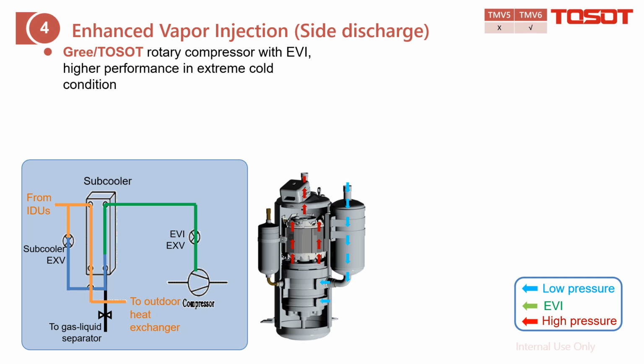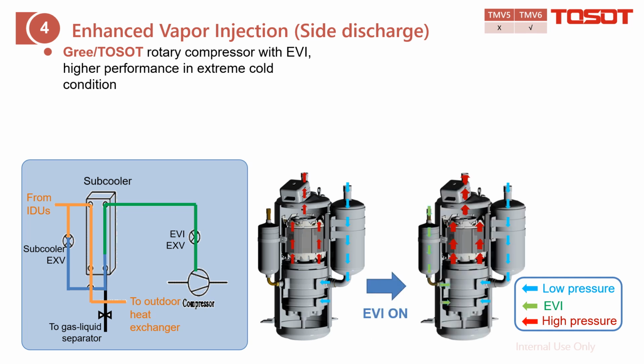As for the compressor, it is from Gree, it is rotary, and this is the regular one without the EVI, which has one inlet. After getting inside, it will get compressed and then get out. After we turn on the EVI, another inlet will join here, then we can make the refrigerant to be compressed out. For this one, you can find that we can get a higher refrigerant flow rate. On the other hand, that means we can get a higher capacity, especially in low temperature.